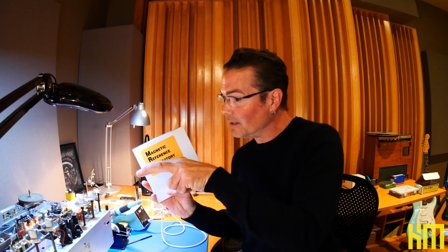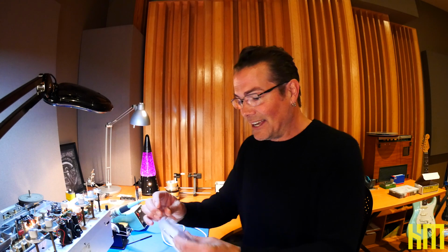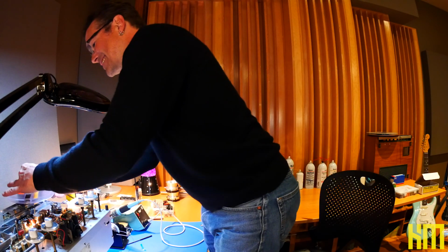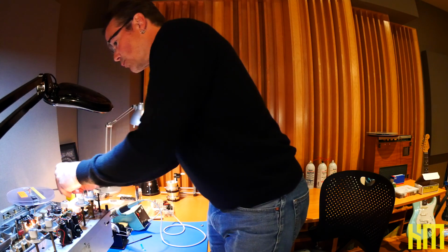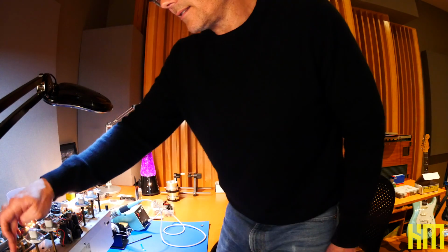So you want to make sure that your record ready buttons are out and in the safe position, right? Don't want to be recording over this thing. This is such an important aspect of doing a calibration. When you're talking about an analog tape machine like this, this is the key. Why? Because this tape was made in a laboratory with a very specific operating level. Let's load this thing up, give it a try. As always, any kind of important master tape, including a test tape like this, is tail out. So I have to put it on the take-up reel and actually rewind that tape in order to use it.